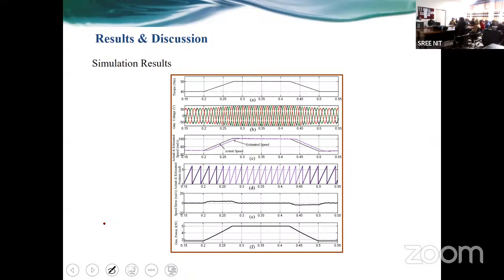If you are going for unregulated control, it is just like a solar pumping water station. Whatever solar power is being generated, accordingly the motor is going to rotate, and accordingly the output water coming from the pipe is changing. So it depends on your load requirement. If you can tolerate the load fluctuations with the voltage fluctuation, that's fine. If you are looking for perfect control, then definitely you need to have some other backup. You cannot manage with this simple load and solar photovoltaic. You cannot do it with that. Are you getting it? That's why a hybrid system, a battery energy storage system, is required.